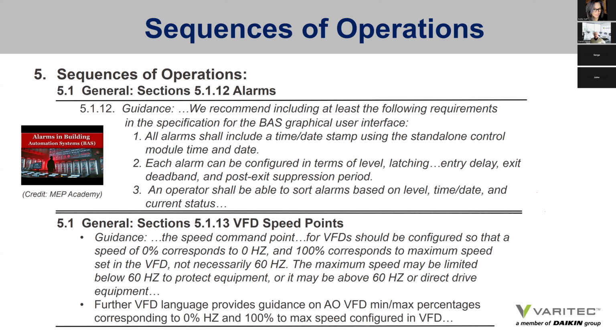The guidance recommends including at least the following requirements in the specification for the BAS graphical user interface: that all alarms shall include a time date stamp using the standalone control module, time and date. Each alarm can be configured in terms of level, latching, entry delay, exit deadband, etc. The sequence of operations, section 5, goes on to address variable frequency drive speed points.